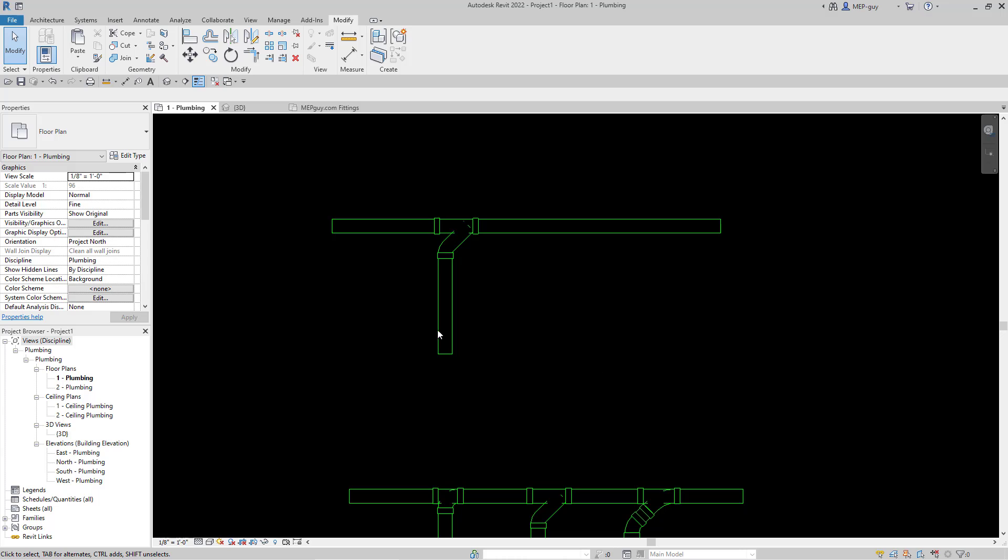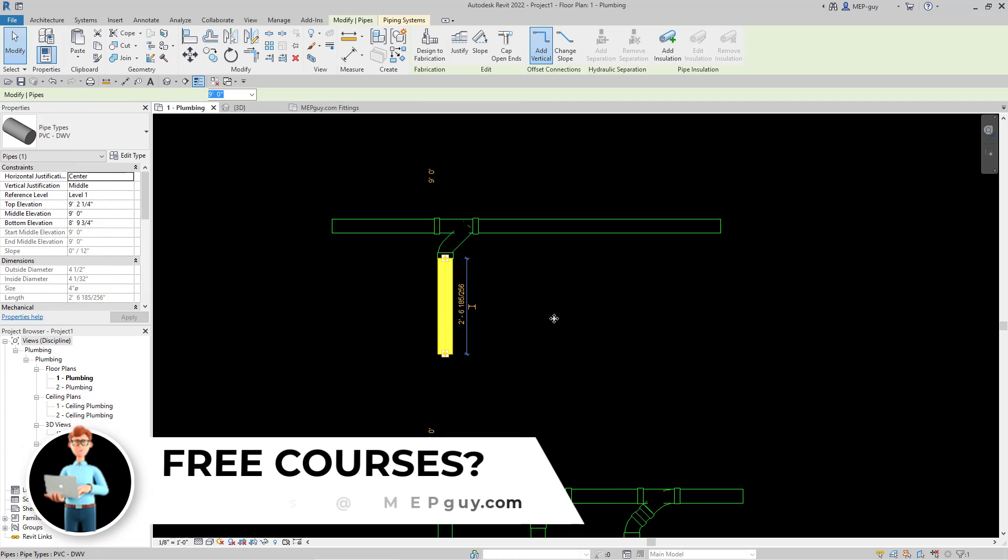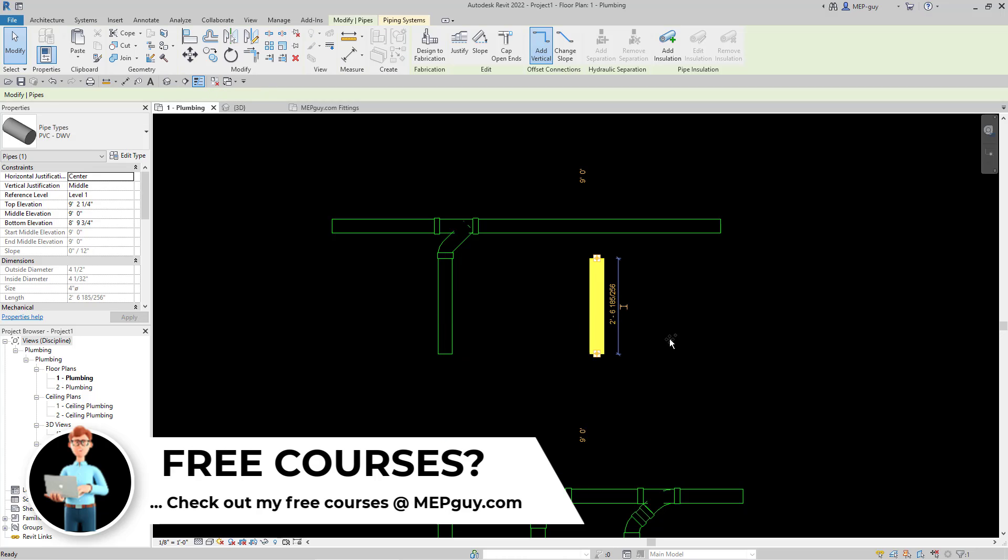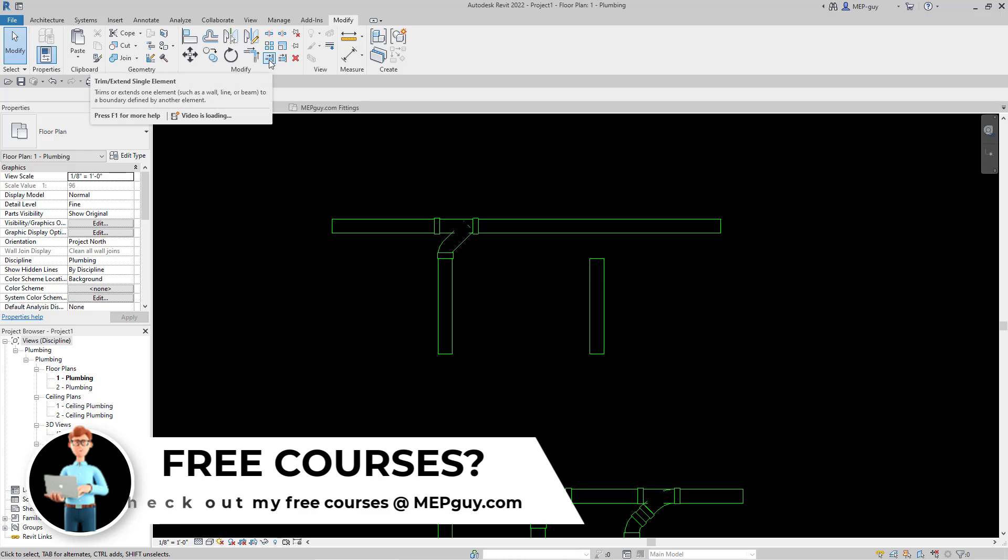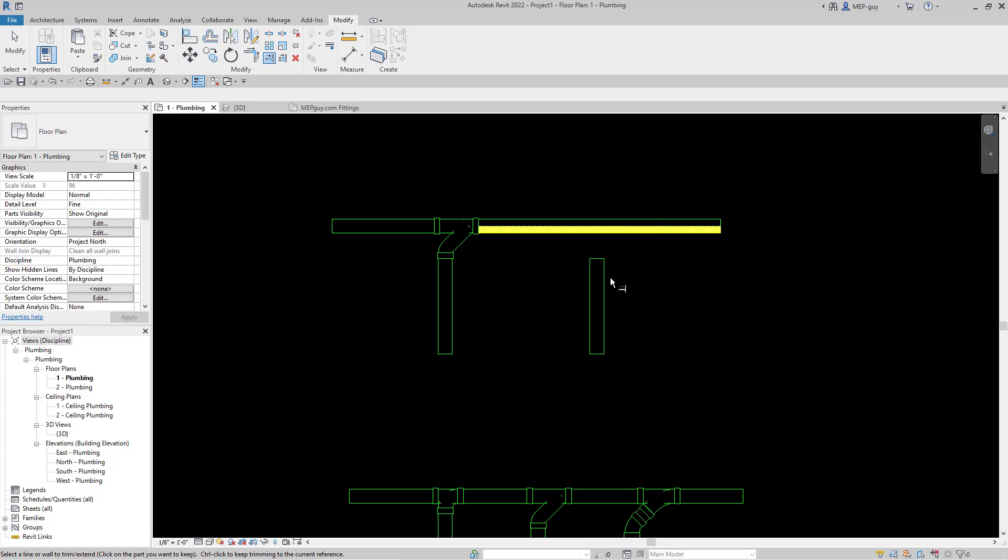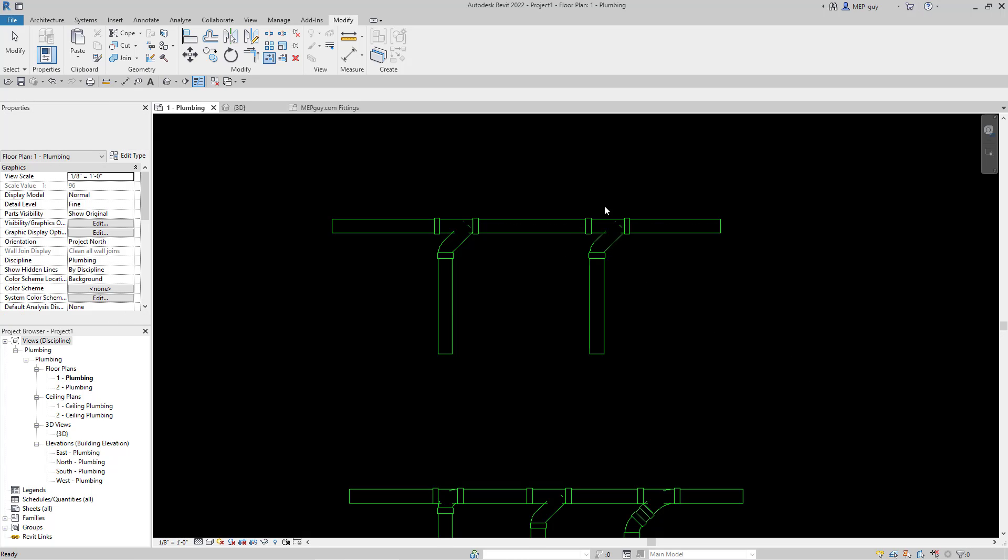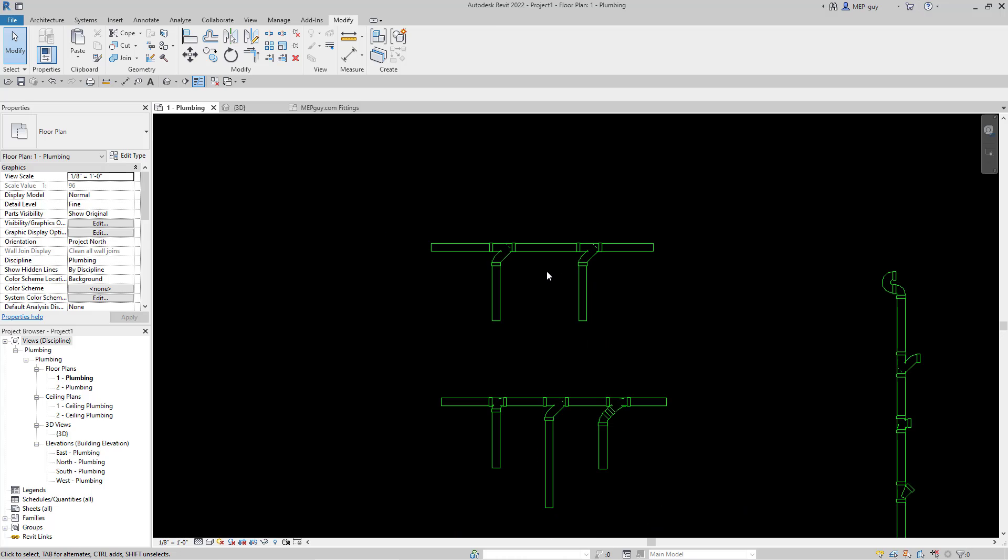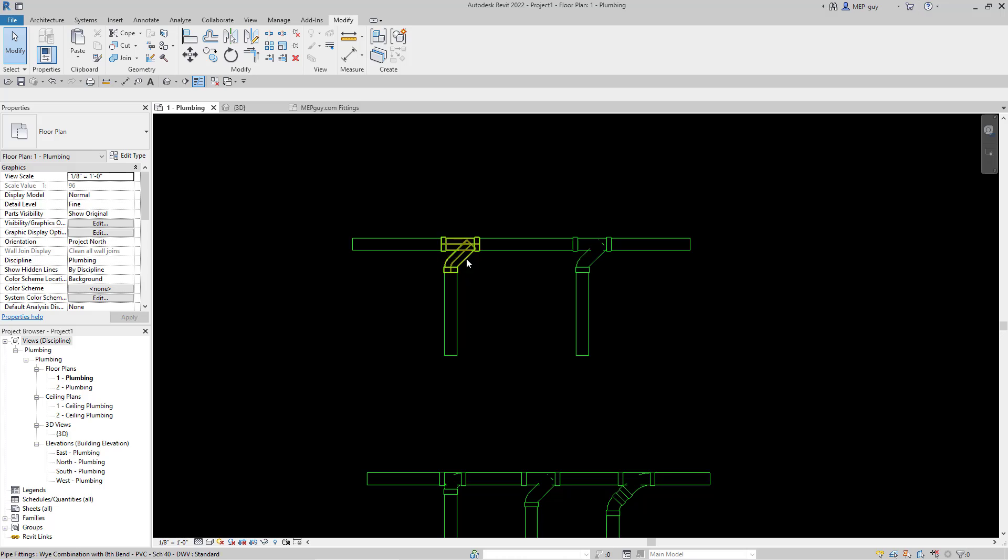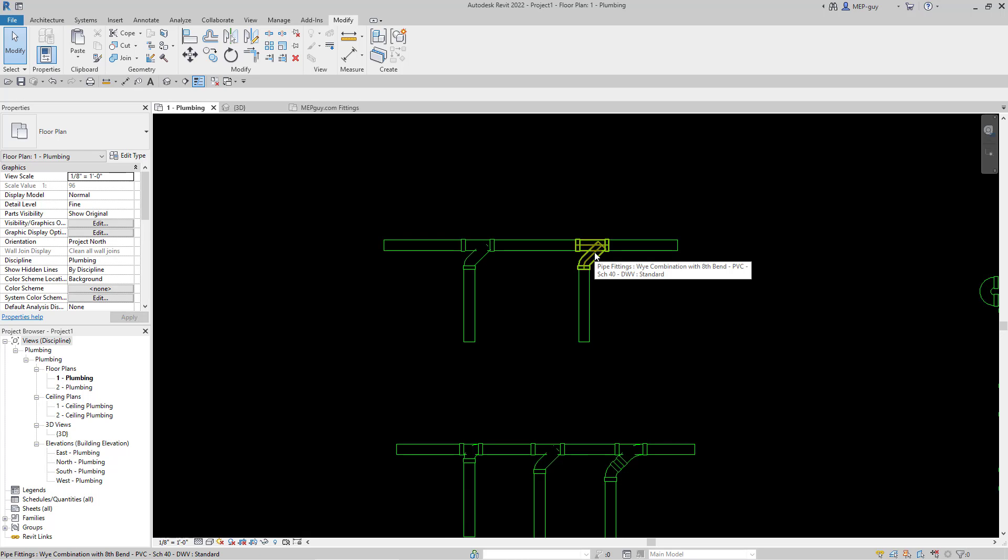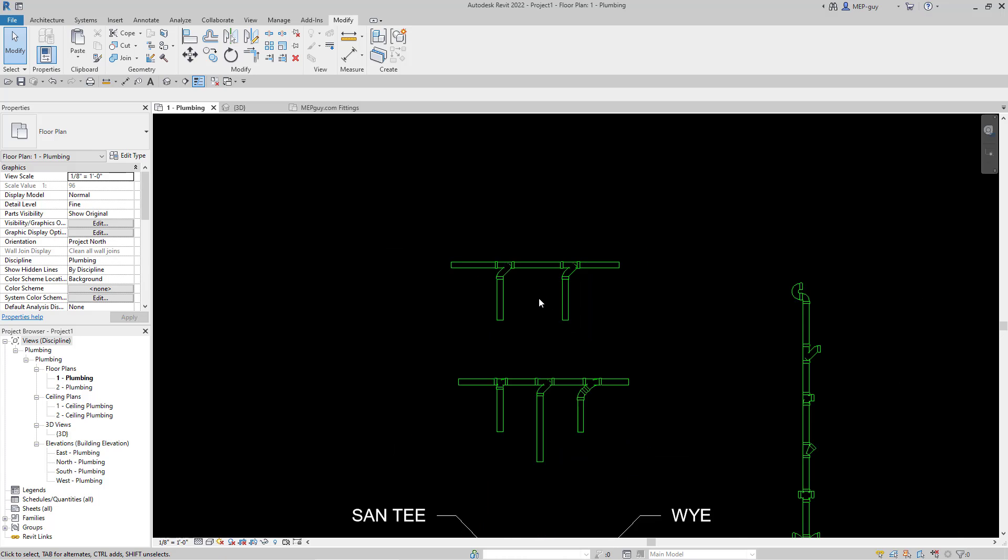Now another cool thing is whenever I have a piece of pipe, so let's just hold control and we'll just copy that piece over here, just like that. Now I can use my modify command and use my trim extend single element. And I'm going to click that, and I can select where I want to go, and then select my piece of pipe. And you'll see Revit will automatically place that fitting. So now when you guys are drawing your horizontal drainage piping, these combination Ys will automatically be set for you. So I would really recommend doing that for your routing preferences, and it'll make your job a lot easier.